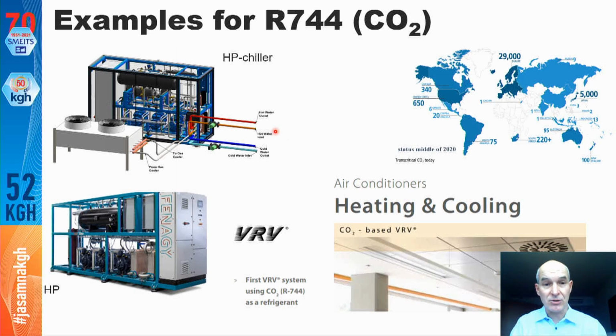On the left I show a heat pump chiller utilizing the benefit of producing hot water at high temperature lift while also producing chilled water at the same time. This can be very energy efficient if you utilize both the hot and cold side simultaneously, which is interesting for example for a hotel, where you need a lot of hot water that you can store, and also need chilling for equipment, rooms, or kitchen.